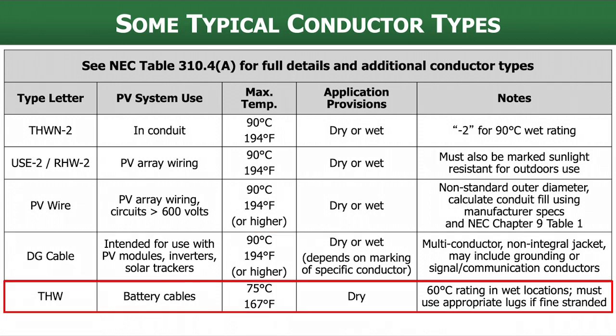Finally, there is THW. We use this for things like battery cables. The key contrast with the other conductor types is that it has a lower temperature rating — it's only 75°C in dry conditions, and in wet locations it drops to a 60°C insulation rating, which can become an issue. Probably we're not putting batteries in wet locations anyway, so that's typically fine. You must use appropriate lugs if the cable is finely stranded, as compared to the normal stranding we see in other conductor types. This is something you may run into when working with energy storage.